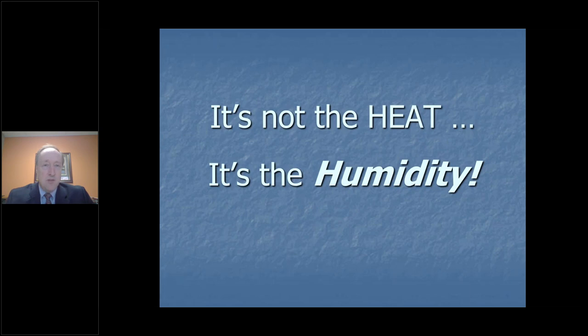Once we put the dehumidifier there and we were delivering air at, I believe, 38 degree dew point, those coils were cold. They were dry. There was no condensation on the coils. They didn't have to clean the coils like they used to years past. These were 8-row coils in that particular air handler. And if you've ever done any coil cleaning, that's extremely difficult, to be able to penetrate 8 rows of coils to get the algae buildup off of those coils. And they were delighted to have shiny coils from that point.